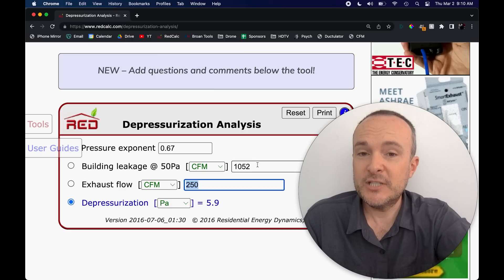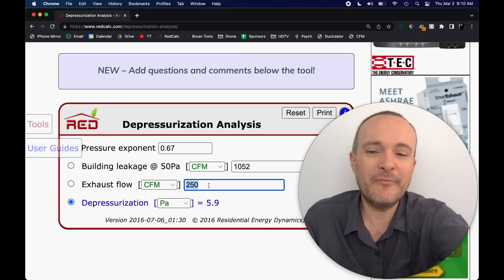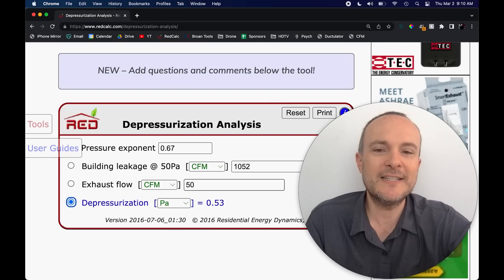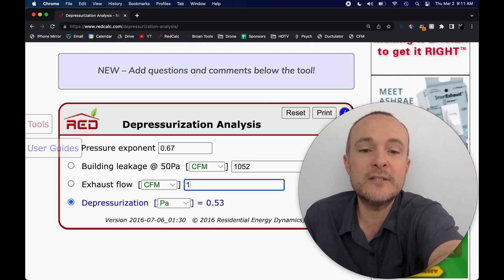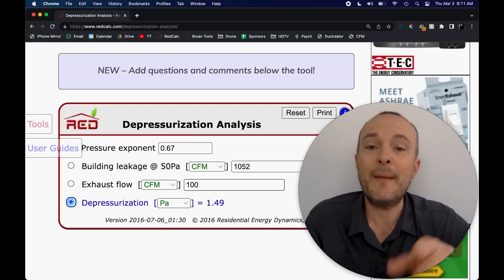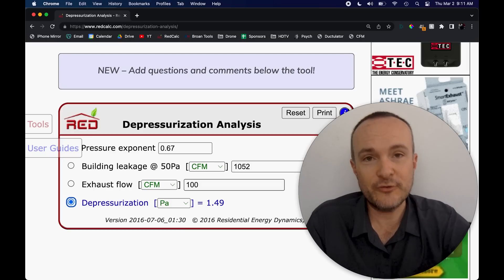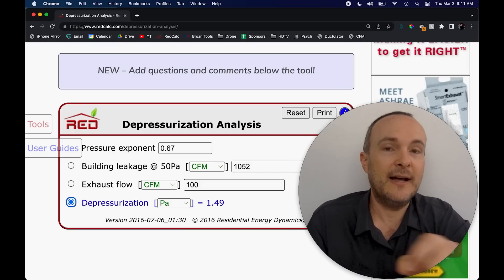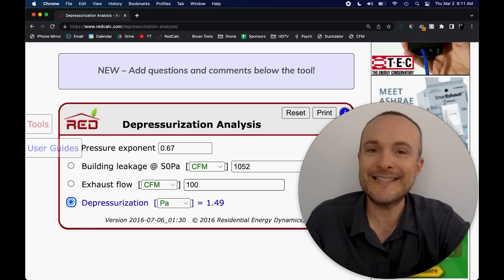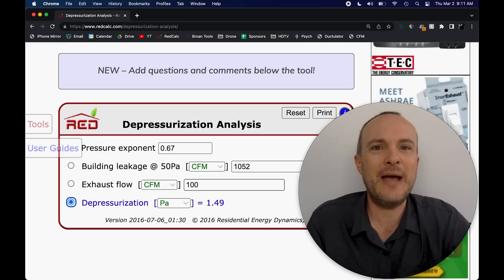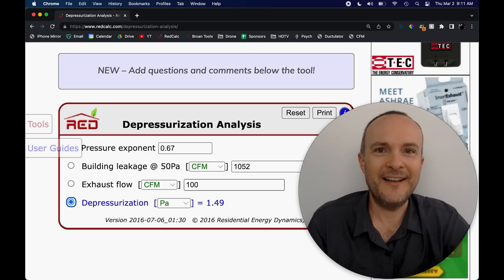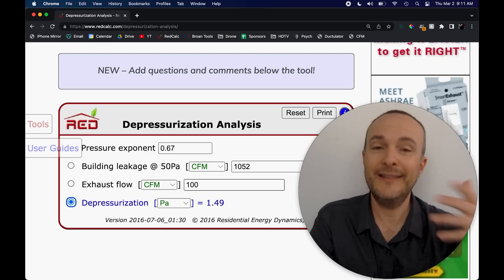Now, if I had all five of my exhaust fans, now I'm running six Pascals depressurization. That is starting to be more of an issue, but of course that's very unlikely. So let's back it off and just see what one exhaust fan does. We're still at half a Pascal. Of course, if I do two exhaust fans at the same time, it's going to bump us up to a Pascal and a half.